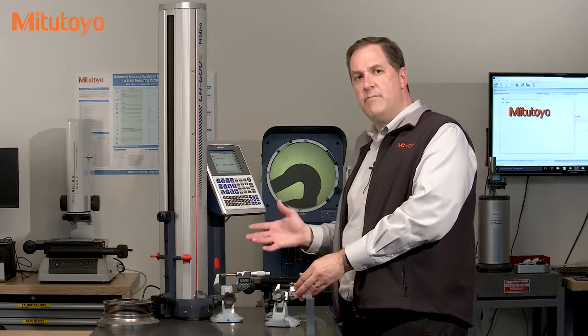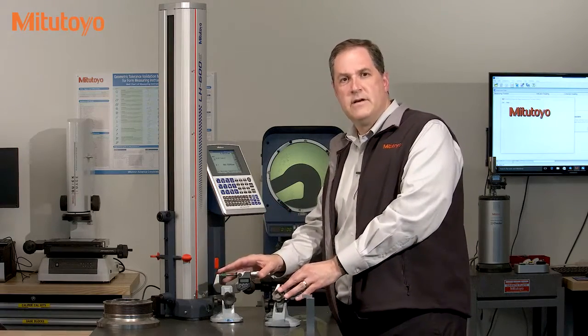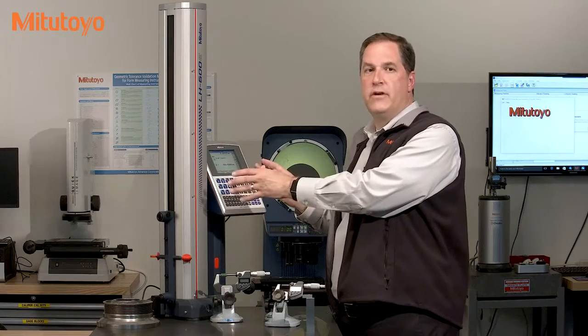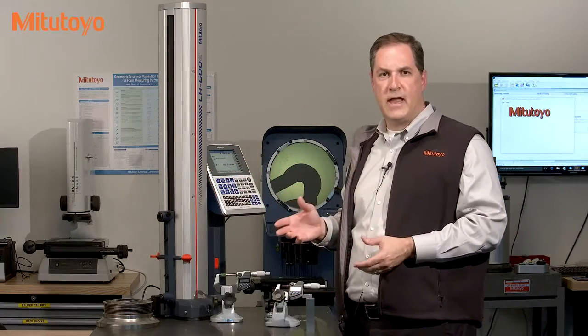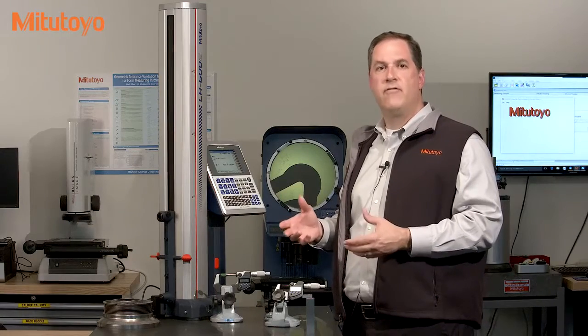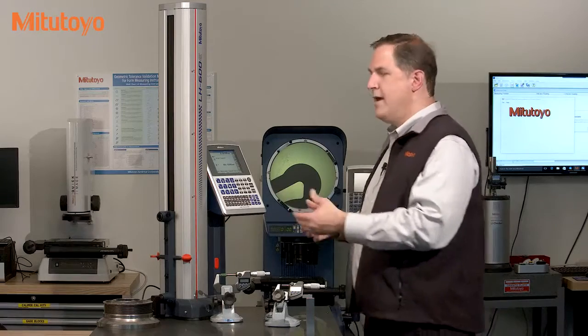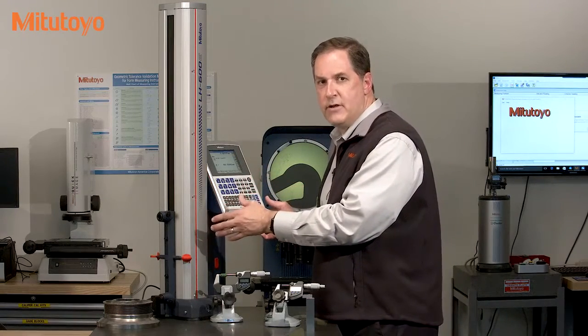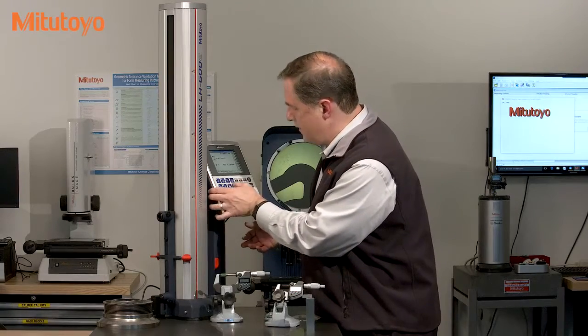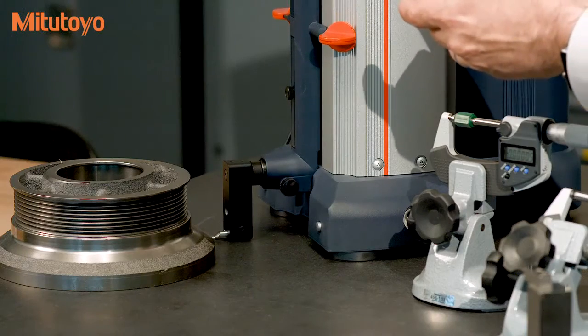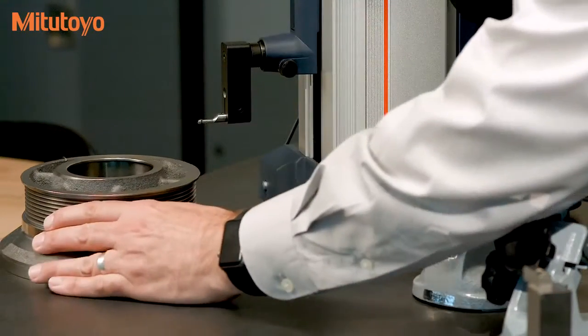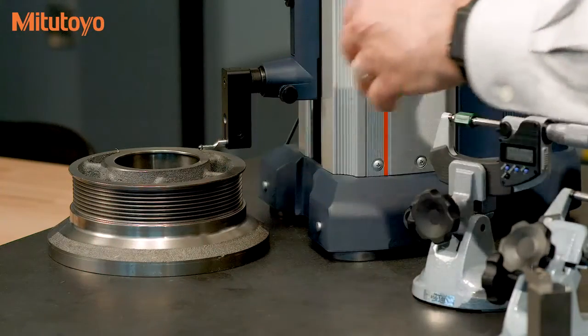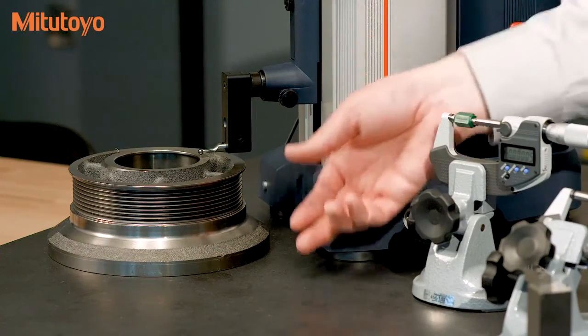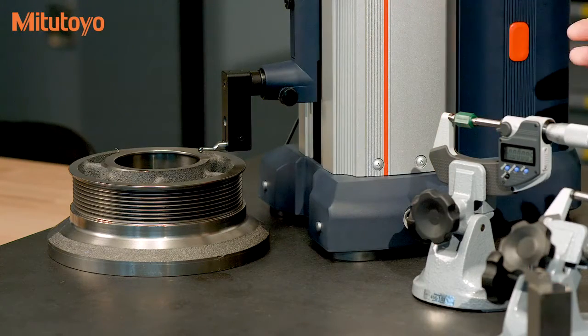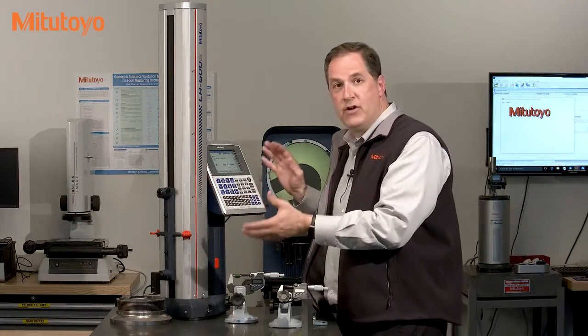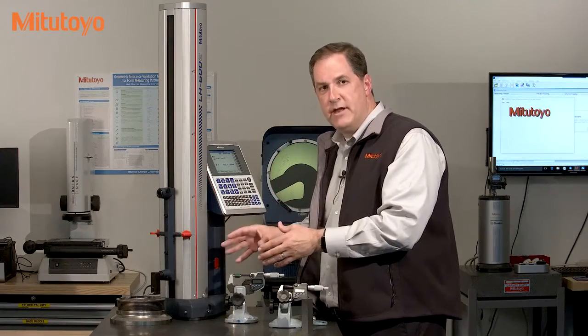Let's use these two common measuring instruments, these outside micrometers and this high accuracy height gauge, called the Mitutoyo linear height, in order to understand the purpose of calibration. We will start by looking at the everyday use of the measuring equipment. Say this linear height is used daily to measure some part like this. I'll measure on the surface plate here, then bring in the part and measure this height. Whoever is using this measuring system wants to make sure the overall accuracy and quality of this measurement process meets their needs.